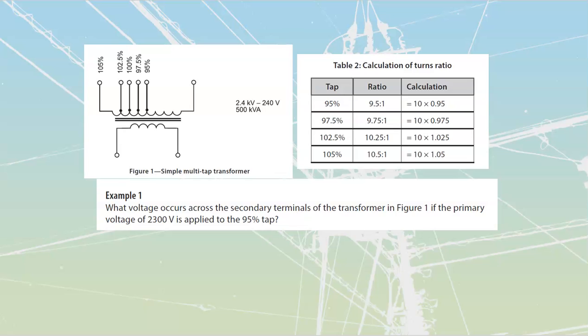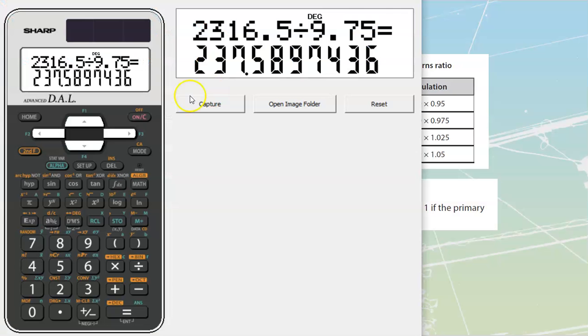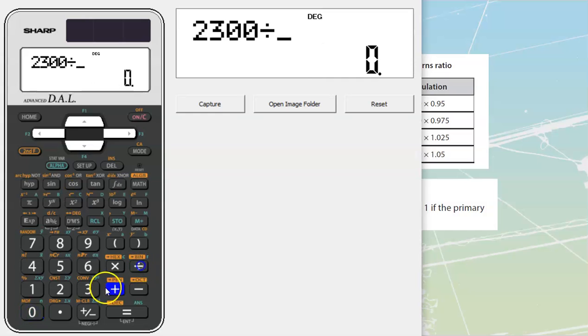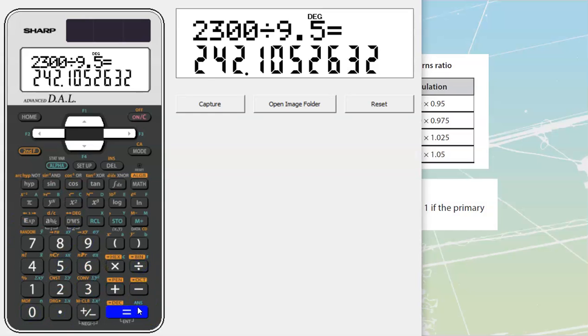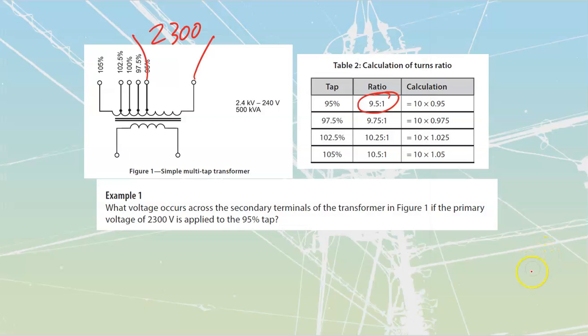Okay, let's go through these questions that they have over here. First example: what voltage occurs across the secondary terminals of the transformer in figure 1 if the primary voltage of 2300 volts is applied to the 95% tap? So we can take this and apply 2300. If it's at the 95% tap, that means my ratio is 9.5 to 1. So take 2300 divided by 9.5, which gets me out to a value of 242 volts.